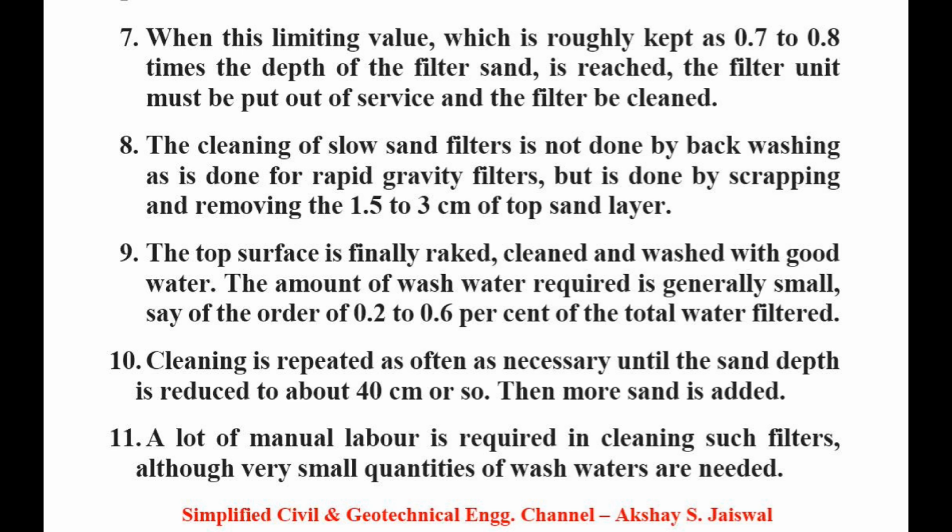The amount of wash water required is generally small, say of the order of 0.2 to 0.6% of total water filtered. Cleaning is repeated as often as necessary until the sand depth is reduced to about 40 centimeter or so. Then more sand is added. A lot of manual labor is required in cleaning such filters, although very small quantities of wash water are needed.